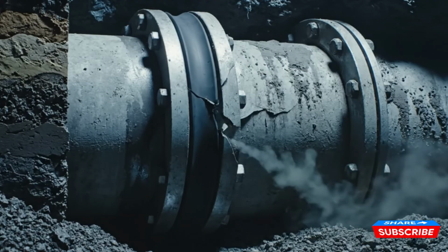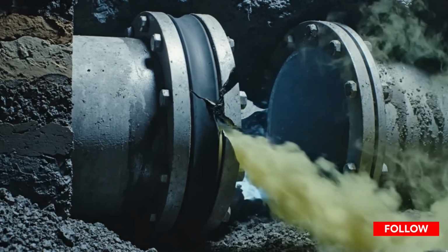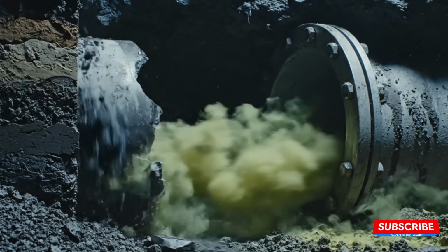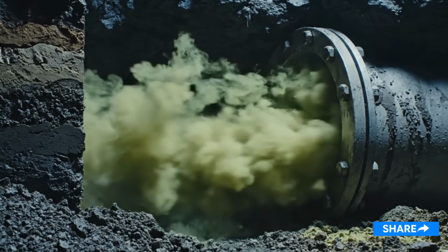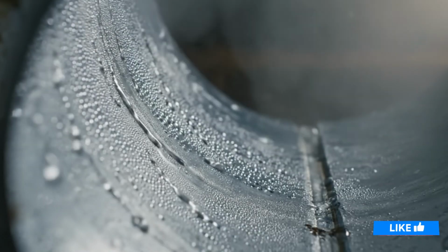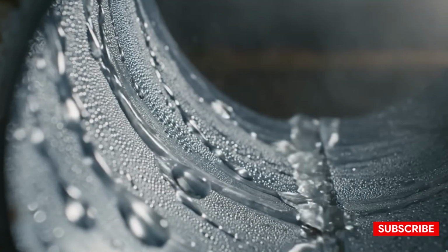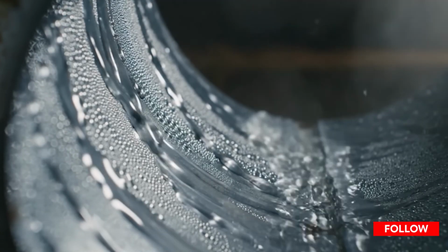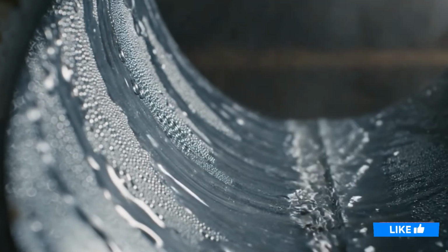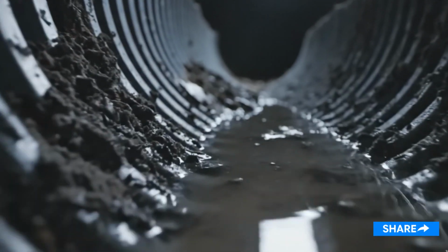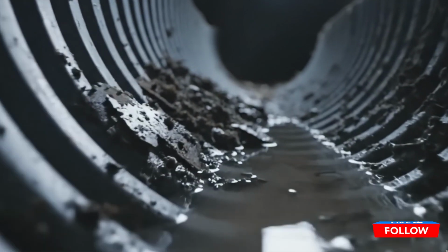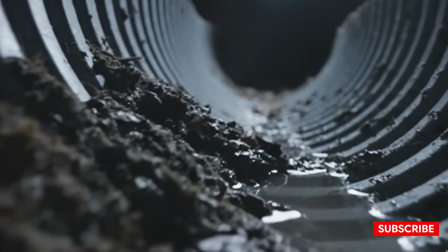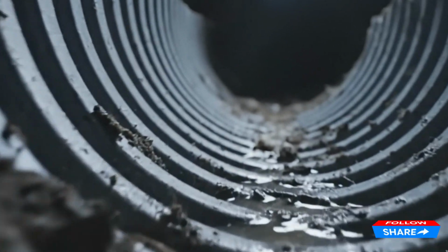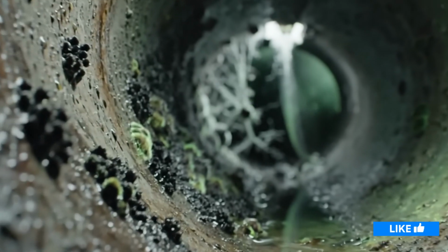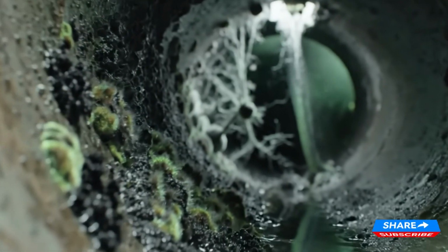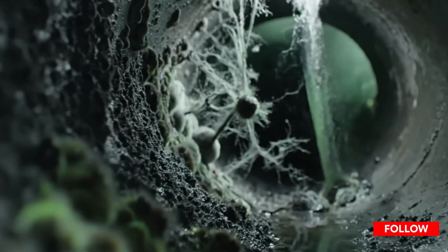And in high radon areas, extra measures, or even a different system design, may be essential. Next comes the piping. This is exactly where many poor installations fail. The buried pipe needs to be smooth on the inside, durable, and completely sealed. Corrugated pipes are a poor choice because their ridges trap water, dirt, and biological growth. A serious system uses smoothbore piping, usually HDPE or PVC, with a diameter large enough to maintain airflow without excessive resistance. Next come two central factors: length and depth.